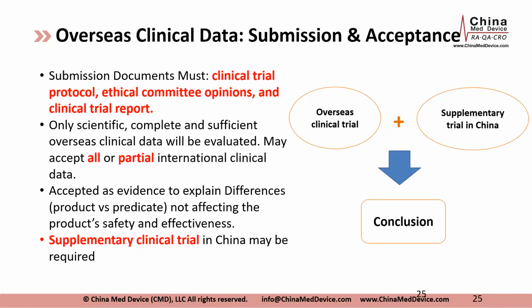So as I mentioned, if you are high risk, class 3, and your device is an innovation, not an evolution, there is an overseas clinical data acceptance pathway. If you've done an overseas clinical trial, maybe you just need a supplementary trial in China. This supplementary trial could be a formal supplementary GCP trial, or it could be a Hainan real-world data supplement. I'll talk a little bit about the real-world data support for the pre-submission supplement.